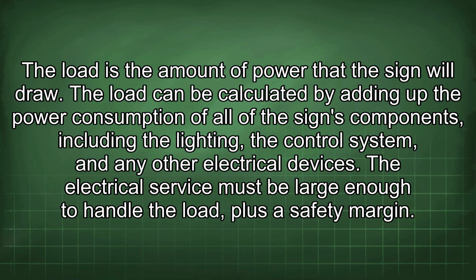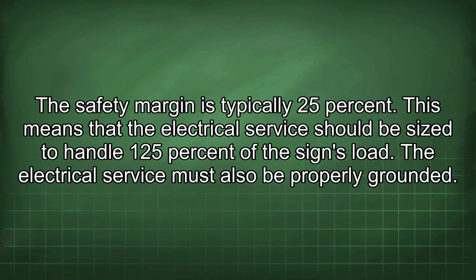The load can be calculated by adding up the power consumption of all of the sign's components, including the lighting, the control system, and any other electrical devices. The electrical service must be large enough to handle the load, plus a safety margin. The safety margin is typically 25%.